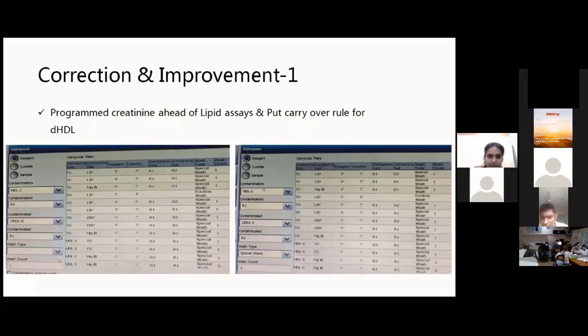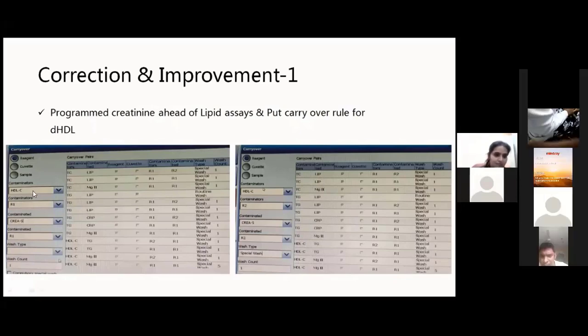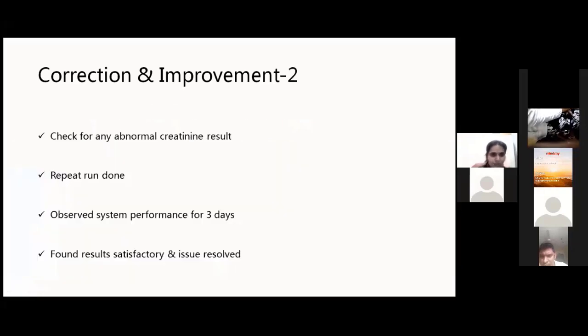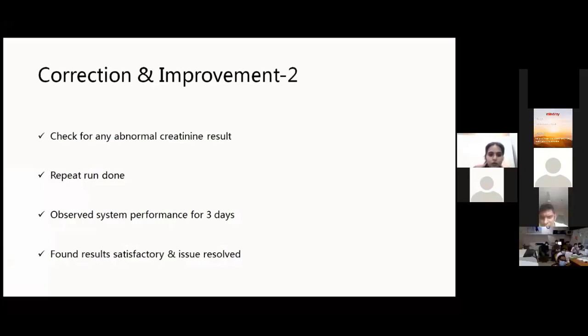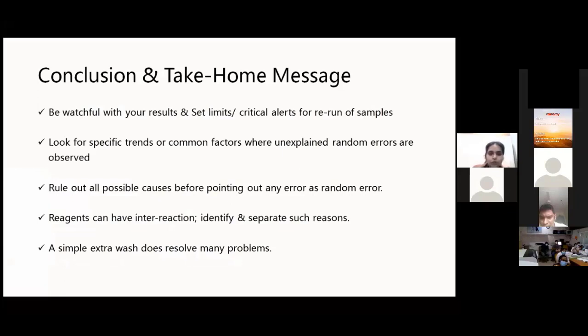So as a corrective action, we programmed creatinine to be run ahead of lipid assays, and then we put a carryover rule for the direct HDL. In our instrument, we have put the rule as HDL is a contaminator for creatinine. Then we checked for any abnormal creatinine results. A repeat run was done, and we observed the system performance for 3 days and found all the results to be satisfactory, and hence the issue was resolved.